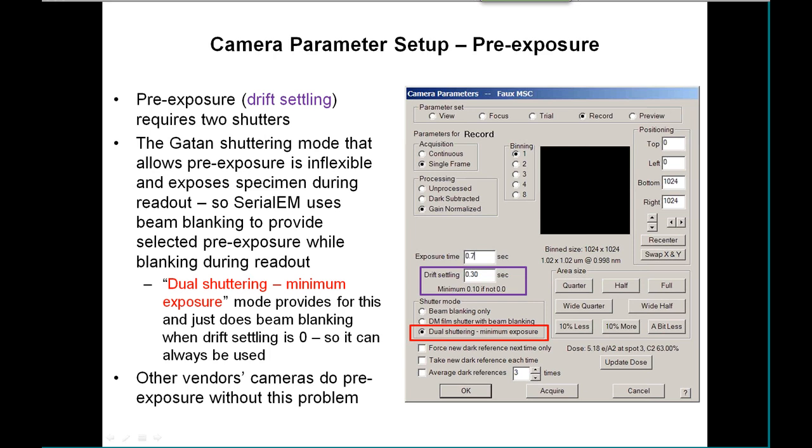Almost always, to do any kind of pre-exposure requires that you have two shutters: one shutter above the specimen that can open before the exposure itself and pre-expose the specimen, and then a shutter below the specimen that doesn't open until we're ready for the actual acquisition on the CCD.